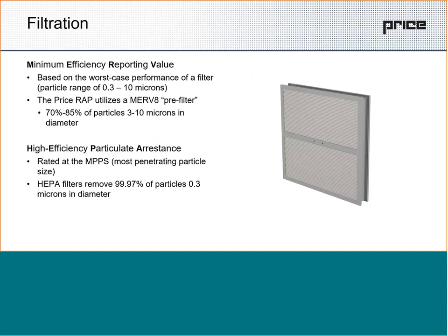Getting into HEPA filtration, I noticed that the more I talk to people about HEPA filtration, even some of the manufacturers that create these portable units, there's not always a great understanding of what the HEPA rating is. The HEPAs in North America are typically rated to capture 99.9% of particles at 0.3 microns in diameter. And there's a common misconception that that is its peak efficiency point, when that is actually its worst efficiency point. The 0.3 micron size is one of the more difficult particles to capture.